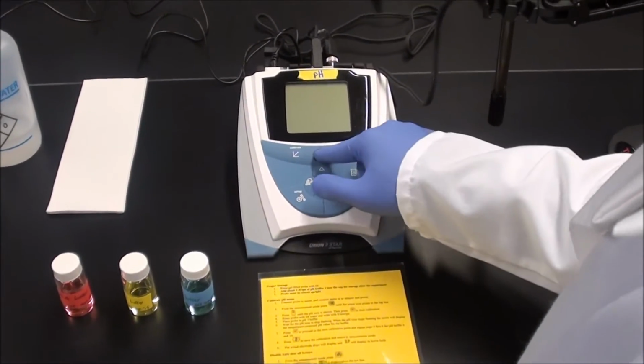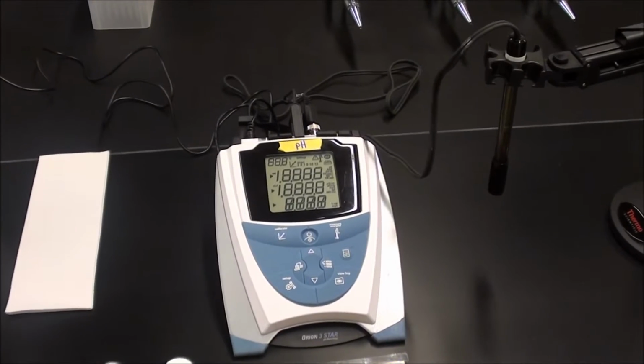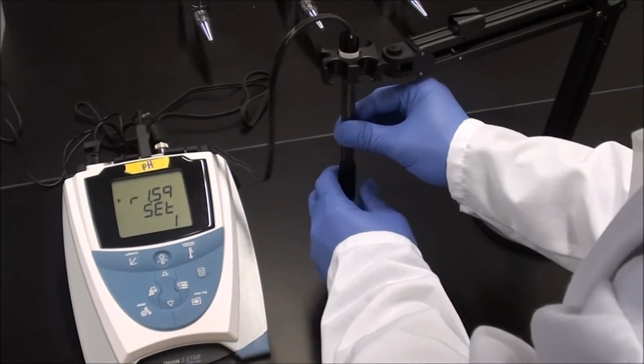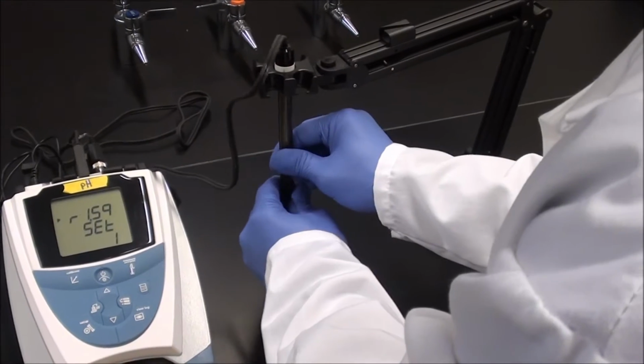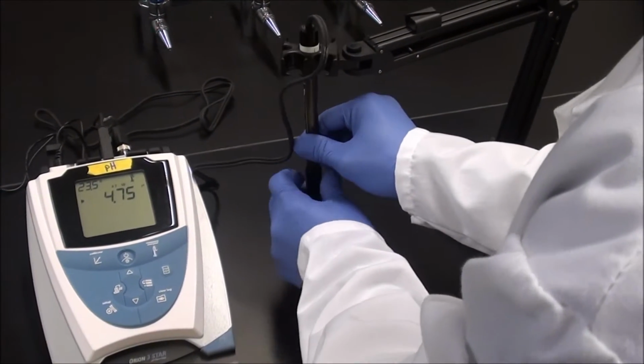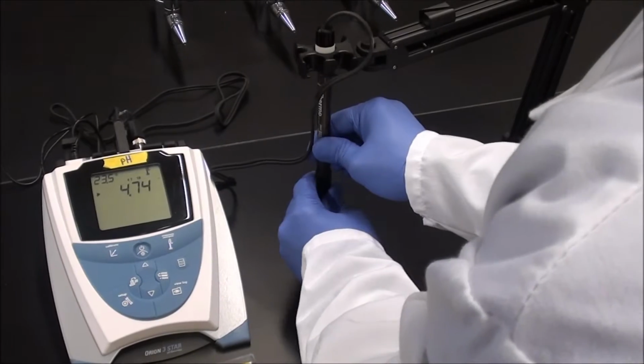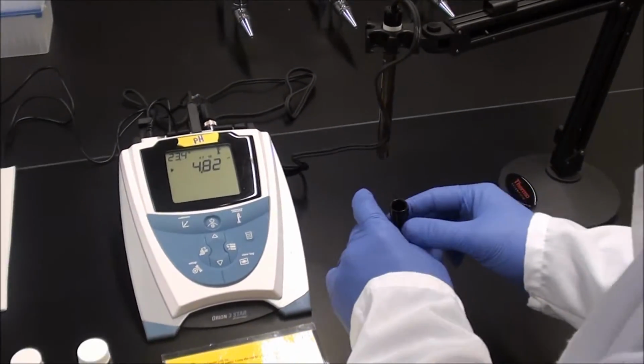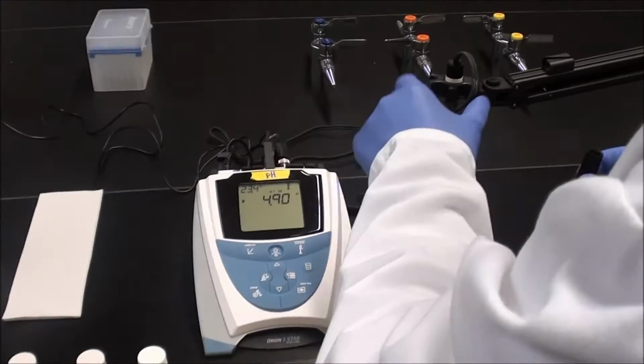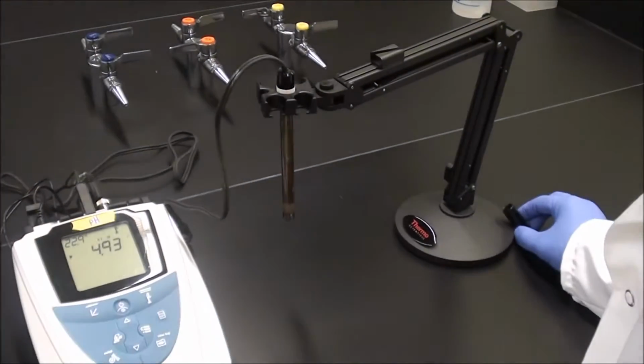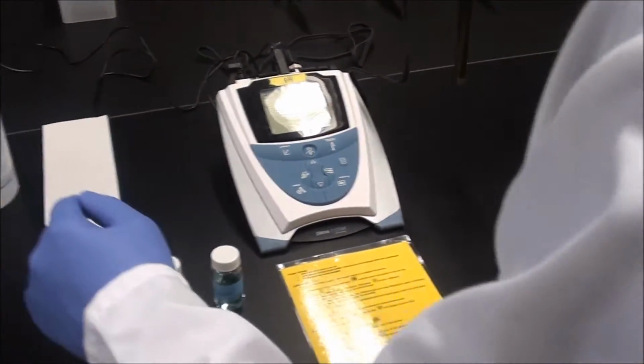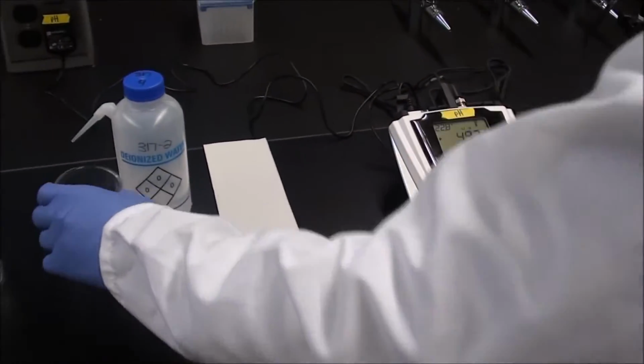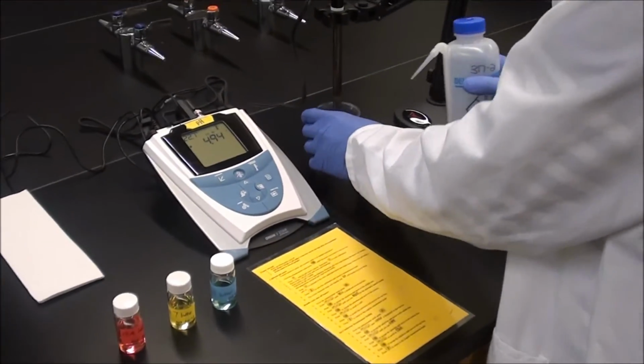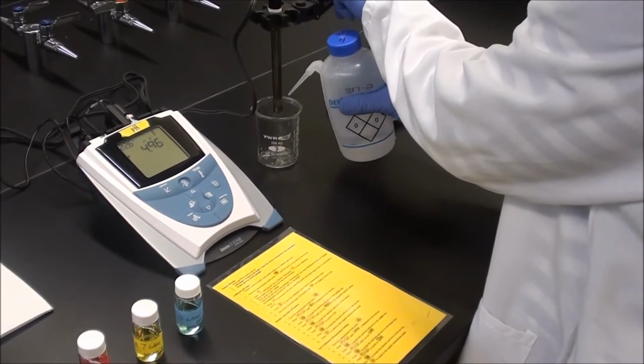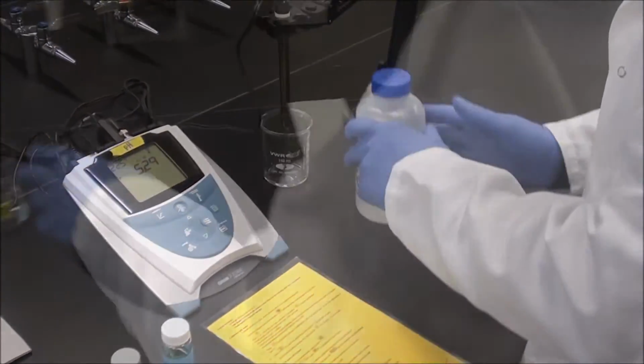So to start off, you turn on your pH meter and you remove the cap on the pH probe. Once you remove the cap, make sure to add about 4 drops of pH buffer 4 into the cap for storage after the experiment. So make sure that you do that once you're done. And then you want to go ahead and rinse the pH probe with DI water. So you make sure to wipe off the pH probe with Kim wipes.